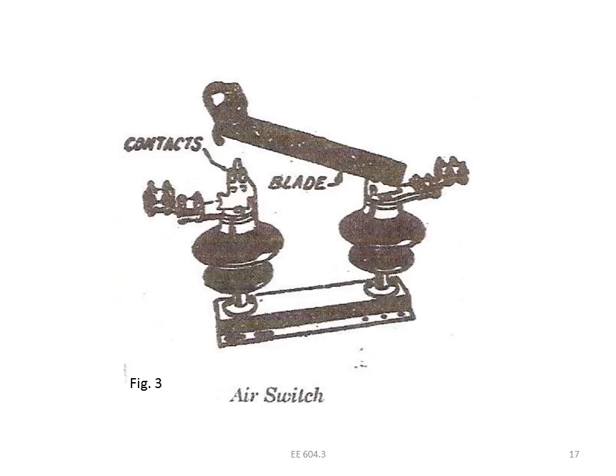So this is the air switch. Whenever the contacts open under load conditions, a high amount of arc will be produced here. This arc causes damage. That's why it should be opened only under no load condition, when there is no current.